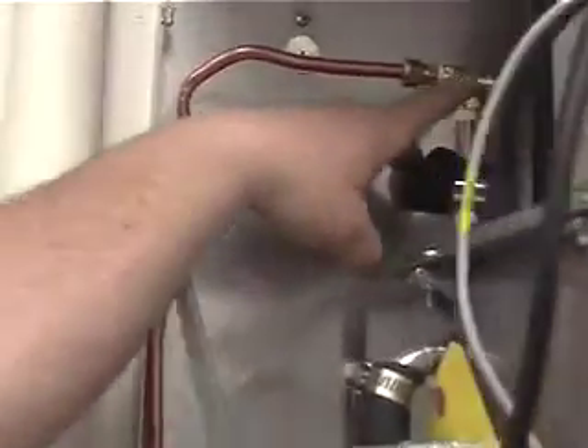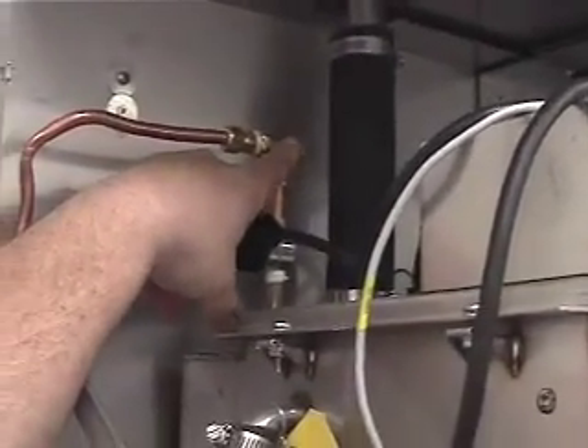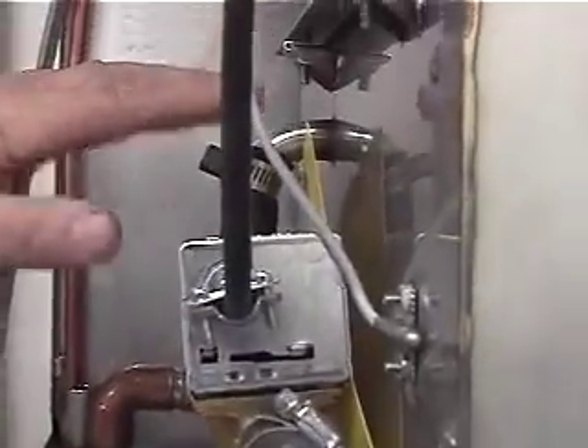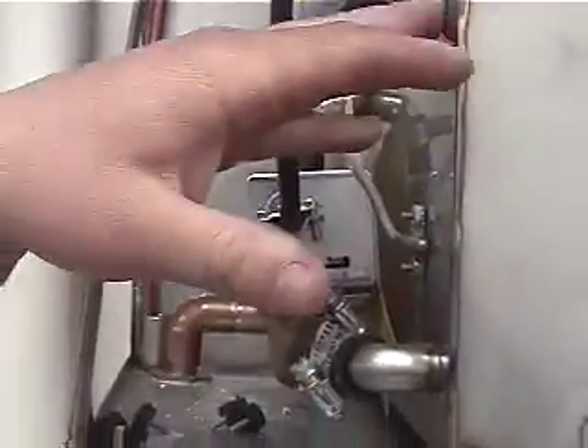So, here on this one we have a fill line coming in here, a solenoid valve to control it. In this T up here in the top, there's a screen. That screen needs to be pulled out and cleaned periodically. It's right here in the back side of this T. So, we have our fill valve that fills it. We have 3 probes inside of this tank that monitor the level. We do it with electronics. So we have a low that'll shut it off. We have a medium that when it gets to that, it fills back to the high point.